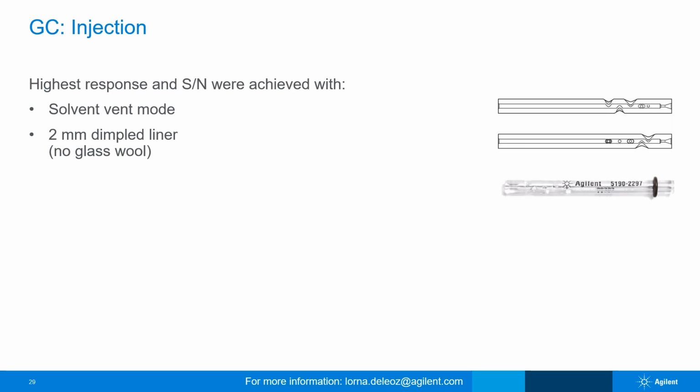Now let's talk about GC injection conditions. We strongly encourage you to use the multi-mode inlet, which enables temperature programming and other injection modes, for pesticide analysis generally, and for pesticide analysis with hydrogen carrier gas specifically.